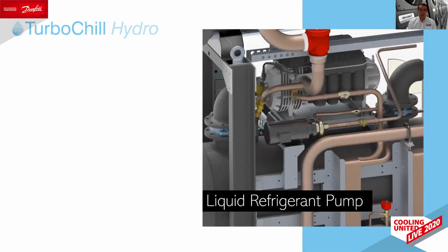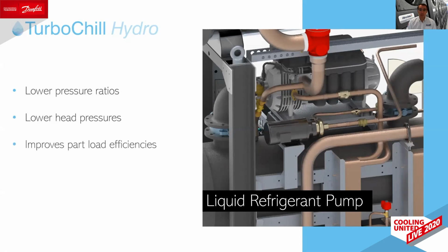I'm now going to introduce the liquid refrigerant pump to you. Liquid refrigerant is passed to the liquid pump from the liquid line and fed back to the compressor motor cooling port. The liquid pump boosts liquid pressure when pressure ratio is low to allow improved turndown and greater part load efficiencies at low pressure ratios. It allows expansion of the compressor envelope, making the chiller more application flexible, and allows faster restart of compressors following power failure, accelerated cooling, and consequently a shorter time to full cooling being resumed.